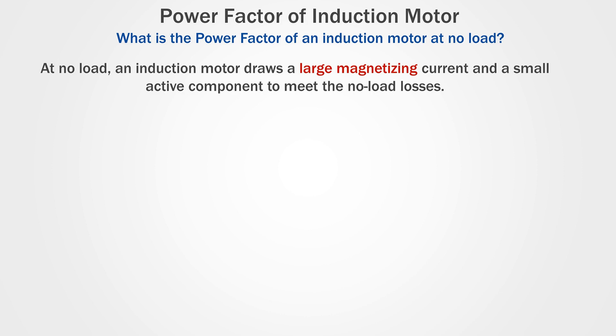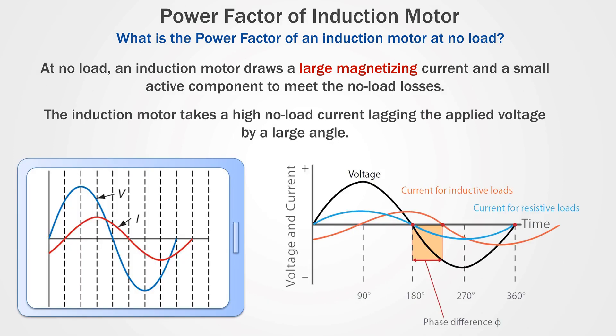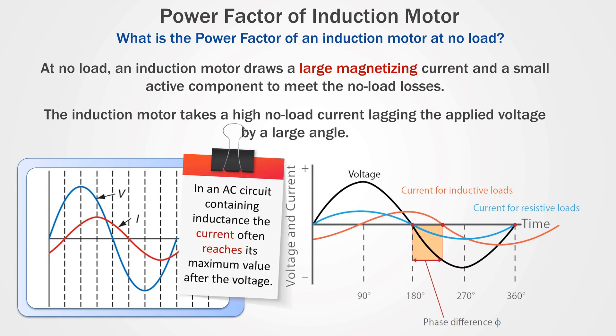At no-load, an induction motor draws a large magnetizing current and a small active component to meet the no-load losses. Therefore, the induction motor takes a high no-load current lagging the applied voltage by a large angle. Hence, the power factor of an induction motor at no-load is low. And as load is added, the active component of current increases, resulting in higher power factor.